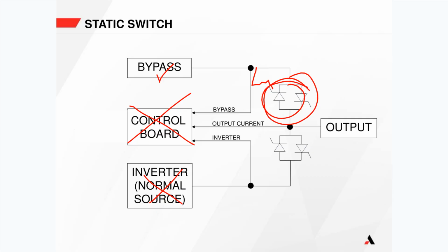from the bypass supply. So we don't use a control logic signal to turn our bypass SCRs on. We self-turn them on using the bypass supply. And basically there's what's called a reed relay in between here. If the inverter is on, this reed relay will be open. But as soon as we say go to bypass, this reed relay closes, and it self-powers the gate drive for these SCRs from the bypass, which we know will be available.